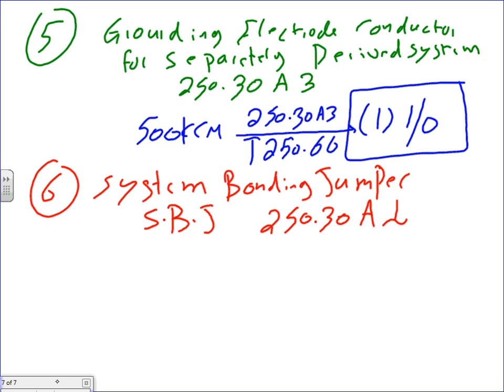The main bonding jumper is when you bring the feeders from the utility, put them in a panel and tie them to ground. That's the main bonding jumper. You tie the neutral to the grounding electrode conductor in the service equipment panel. The calculation is the same, guys.